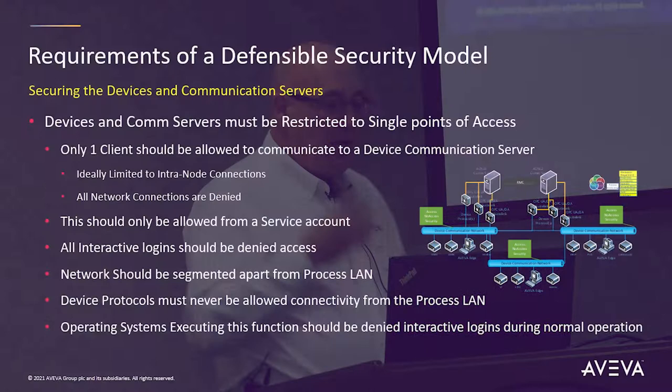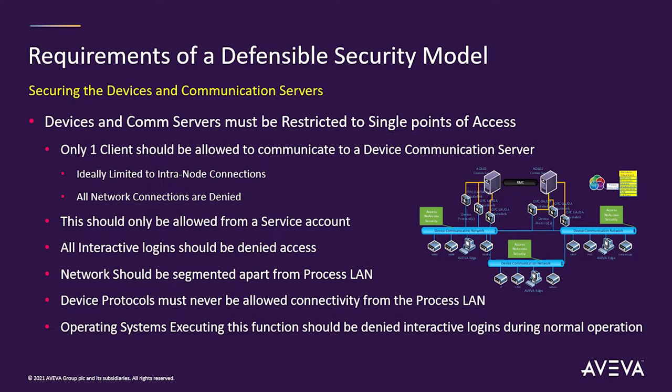As we look at this environment, my blue network is my device network. You should really design this so there's one entity that talks to that device network — a service account. I shouldn't allow interactive logins to communicate to that device network. It should be a service account at the point of who's allowed to talk to that IO server. That network should be segmented from the process LAN. Any operating system that's allowed to operate a COM driver like that should be denied interactive login — there's no reason to be logging into that thing.